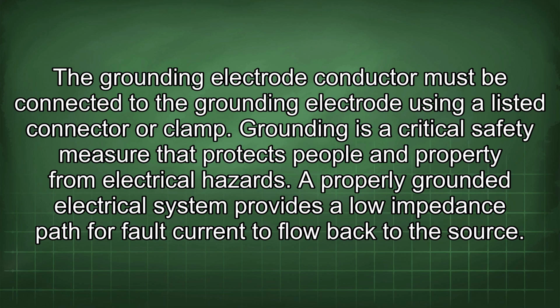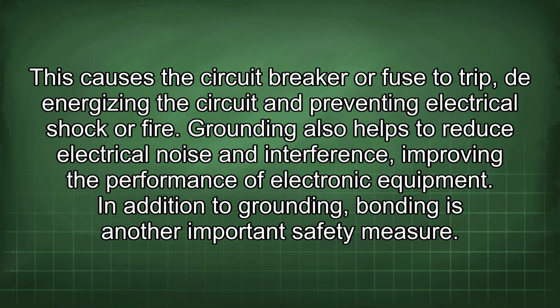A properly grounded electrical system provides a low impedance path for fault current to flow back to the source. This causes the circuit breaker or fuse to trip, de-energizing the circuit and preventing electrical shock or fire. Grounding also helps to reduce electrical noise and interference, improving the performance of electronic equipment. In addition to grounding, bonding is another important safety measure.